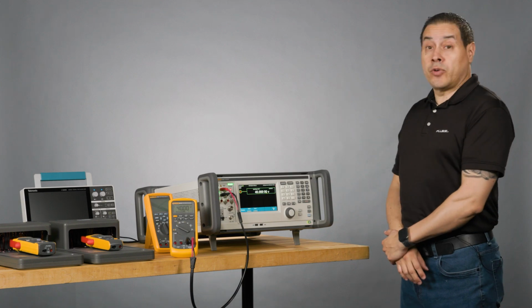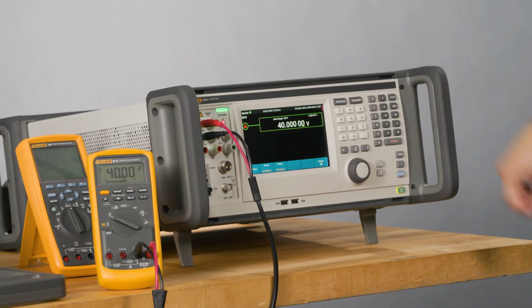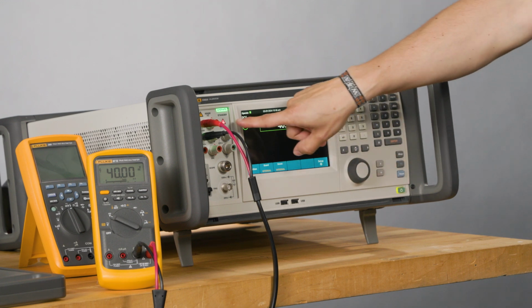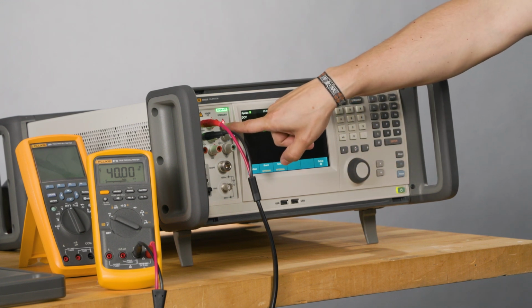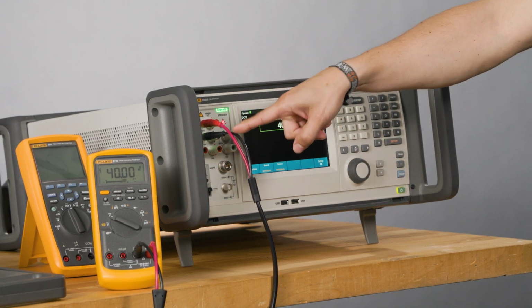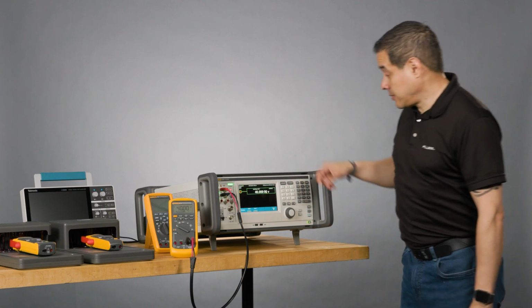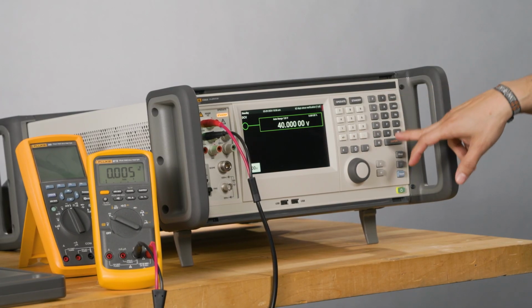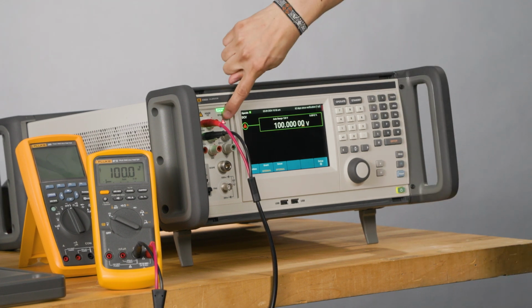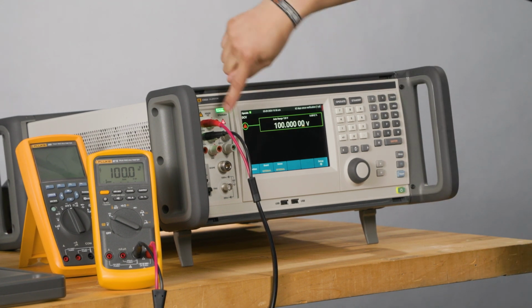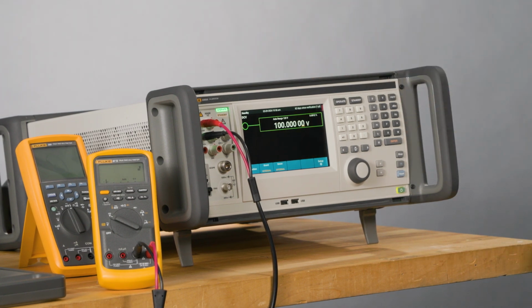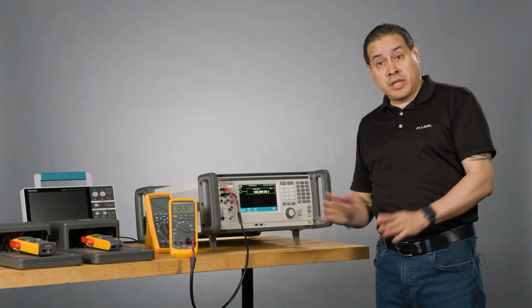So now I'm calibrating 40 volts. I need to check that 40 volts there, get my numbers. If you notice, this light turns on, which means that it is potentially dangerous. Be careful, use the protection. 100 volts, DC. I get my indication that it's dangerous. 100 volts, we're good.